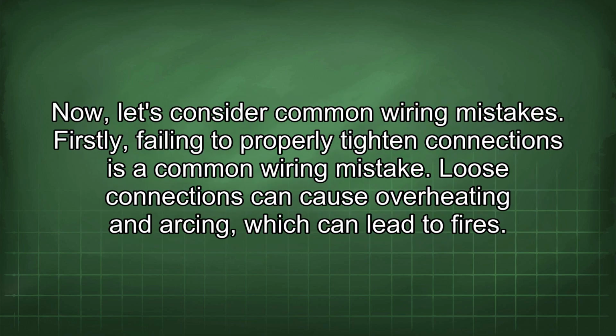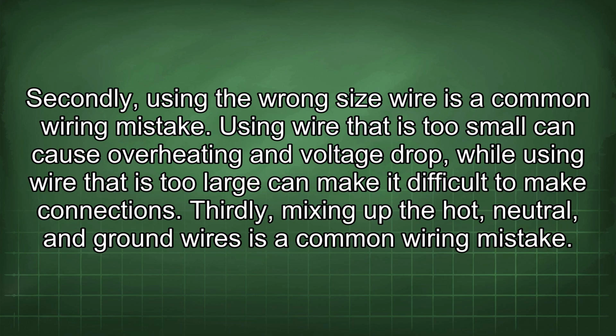Now, let's consider common wiring mistakes. Firstly, failing to properly tighten connections is a common wiring mistake. Loose connections can cause overheating and arcing, which can lead to fires. Secondly, using the wrong size wire is a common wiring mistake. Using wire that is too small can cause overheating and voltage drop, while using wire that is too large can make it difficult to make connections.